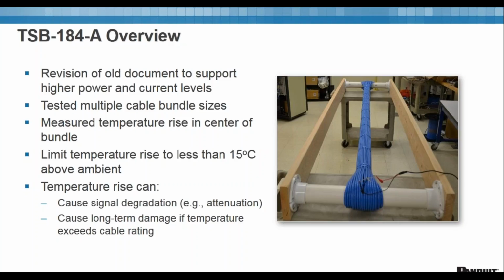So the recommendation per that standard is to really limit temperature rise to less than 15 degrees Celsius above the ambient temperature. What that ensures is that, if you have a temperature rise, it can lead to signal degradation, which means more insertion loss or attenuation on your system, which in turn limits how far it can go. And temperature rise can also cause long-term damage to the cable if it exceeds the rating, which is uncommon.